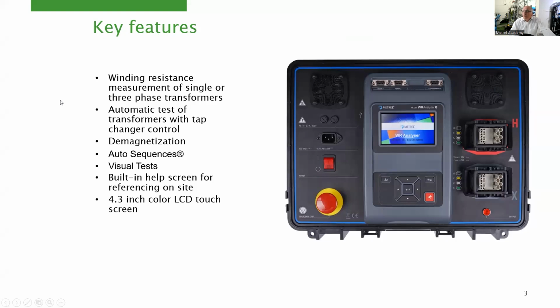Once again, the key features: winding resistance is the main feature of this instrument. We can perform automatic tests with the control of the tap changer. We can demagnetize the transformer after the measurements. We can use auto sequences. We have visual tests supported, and so on. With the classic 4.3-inch color LCD touch screen display, which is the typical standard user interface for Metrel instruments.